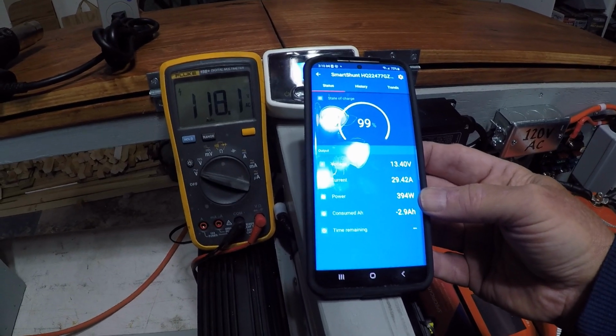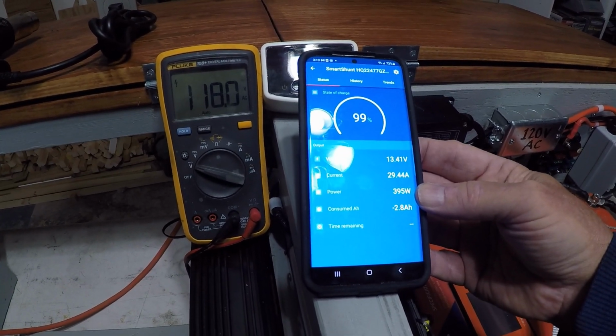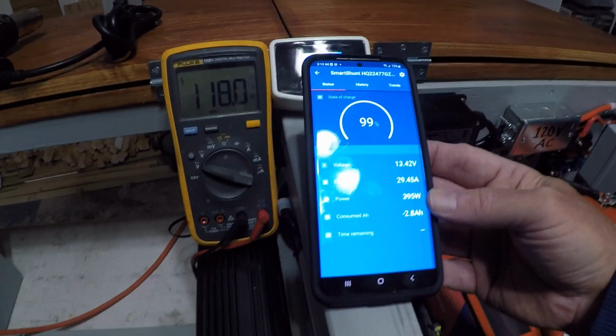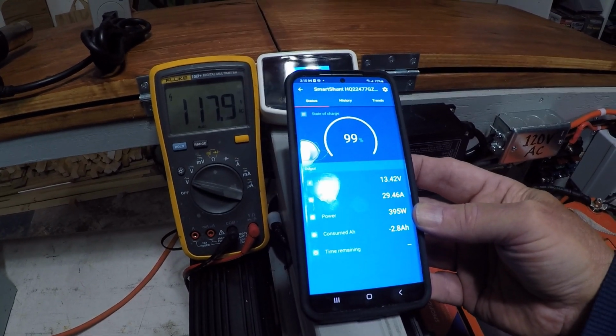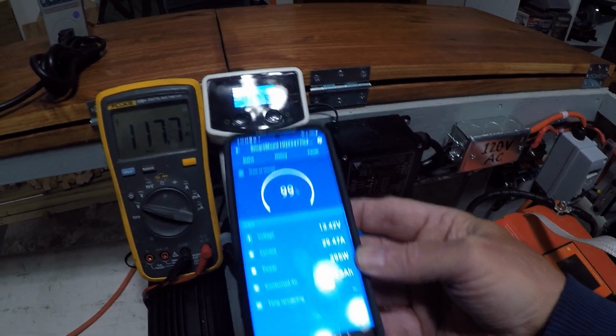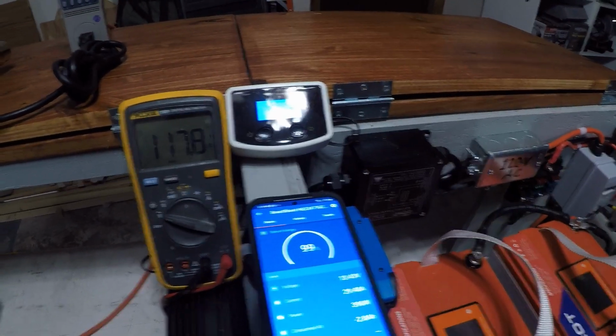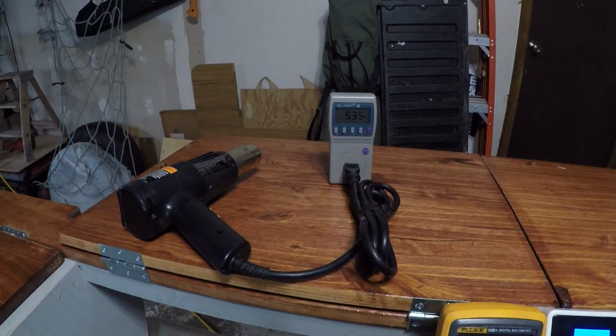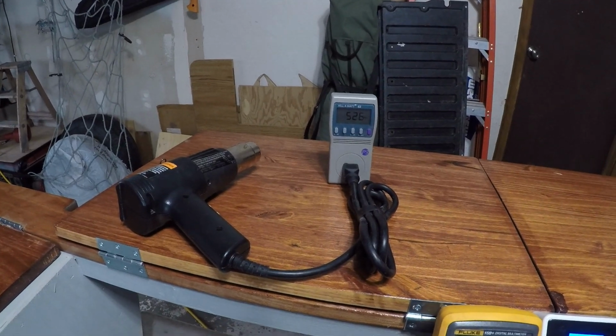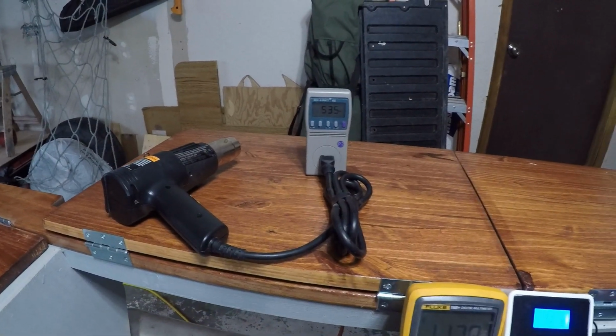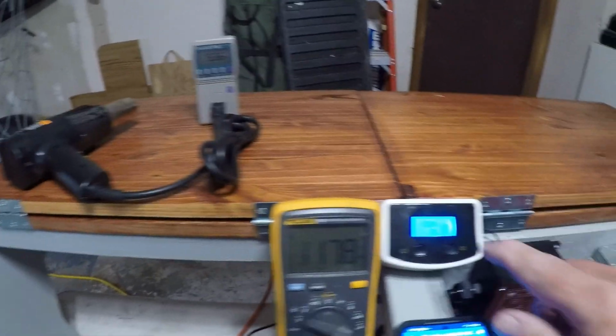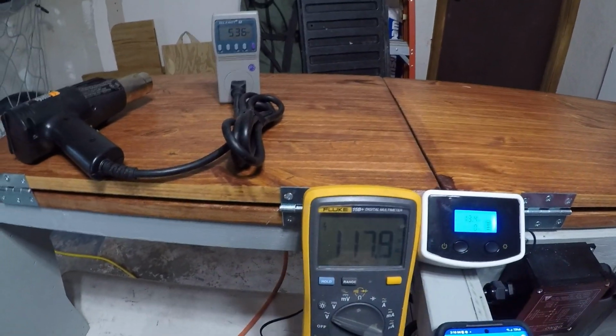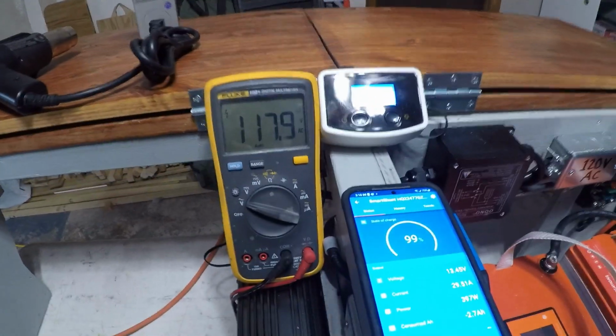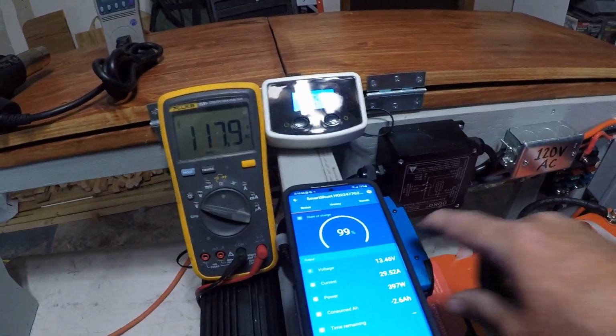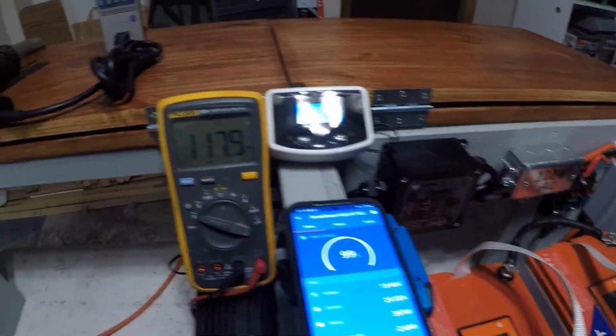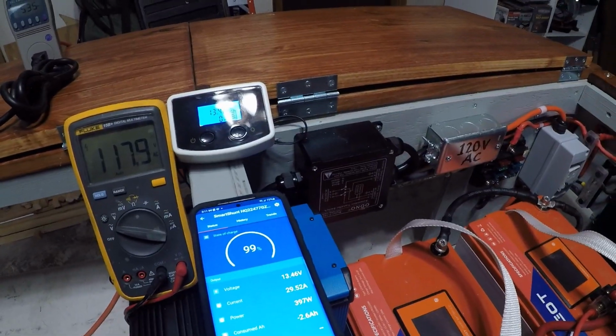So by turning that switch, we got off the batteries onto shore power. The three-way switch turned over here, and now we get our 535 watt load being run off of shore power. It's not the inverter — the inverter's still got voltage, but it's idling, not doing anything. And our 30 amp charger is automatically switched in to start charging the batteries again.